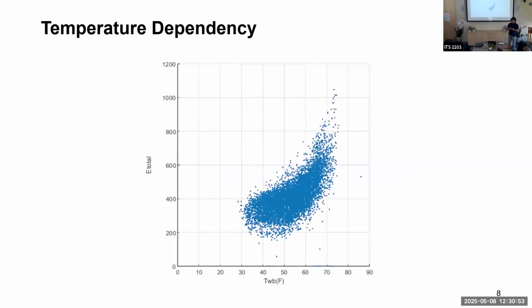And the cooling largely depends on the outside temperature. So this is just the total kW of the facility, which includes everything, and on the x-axis I have the wet bulb temperature outside. It looks like there's maybe a quadratic relationship between those two. So when the temperature goes up, the facility electricity draw goes up. And if you're a mechanical engineer, I think I see an airfoil design here as well.